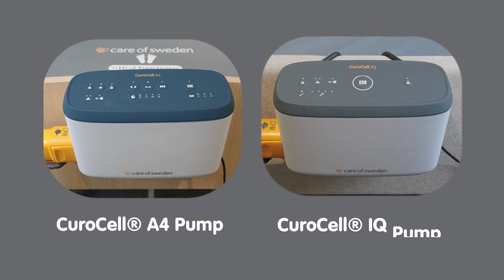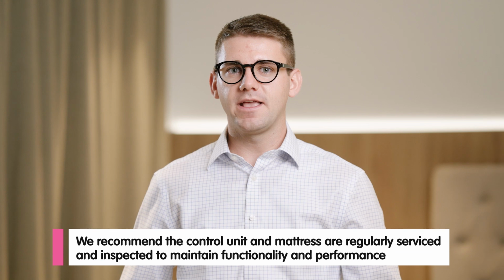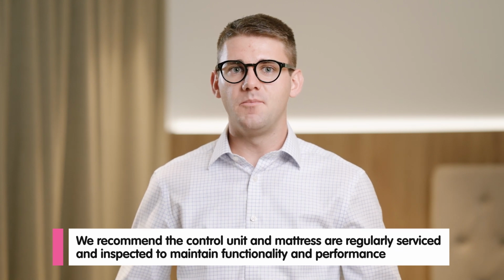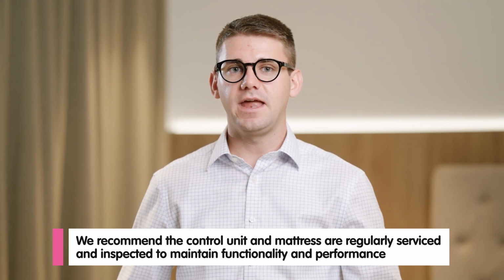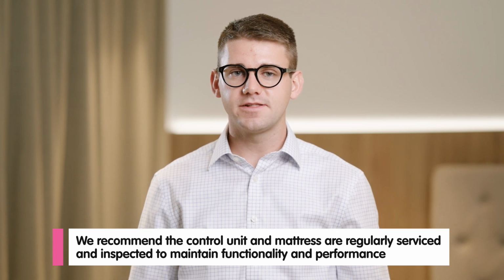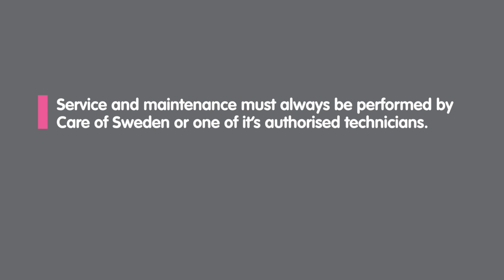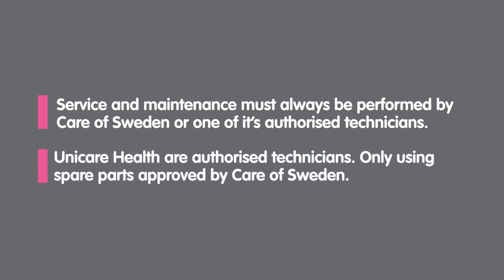In this video, we will talk through some basic maintenance and troubleshooting steps you can take to ensure your pumps run at an optimal level. We recommend that the control unit and mattress are regularly serviced and inspected to maintain functionality and performance. Service and maintenance must always be performed by Care of Sweden or one of its authorised technicians. Unicare Health are authorised technicians and we only use spare parts approved by Care of Sweden.